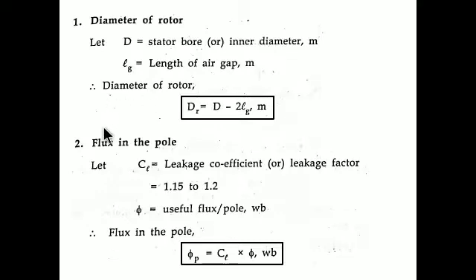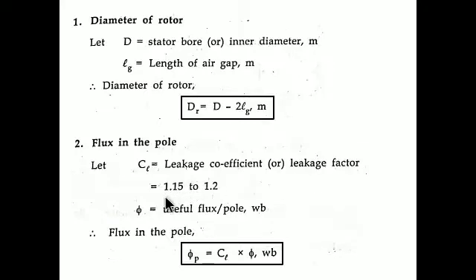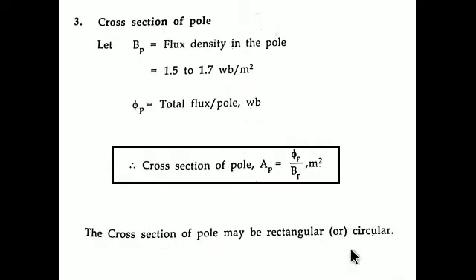The second step is flux in the pole, denoted φp. It is defined as the product of two things: the leakage coefficient Cl and the useful flux per pole φ. The leakage coefficient Cl, also called the leakage factor, is an assumed value lying between 1.15 to 1.2. The useful flux φ is in webers. So φp = Cl × φ gives us the flux in the pole.